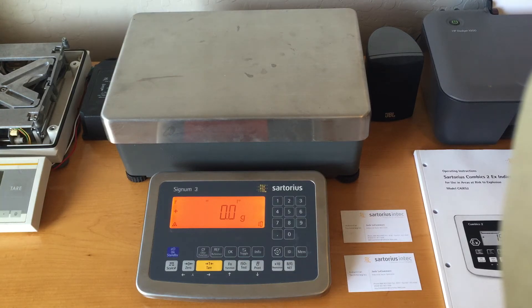It was a quick reset — it put us into the service cal mode. Now when you press and release the ISO test key, it will actually bring you to a place where you can select the type of calibration you'd like to engage.